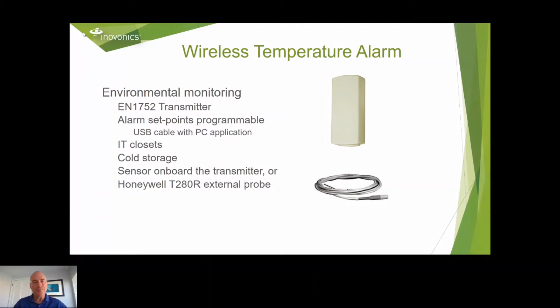Then you can also go to our website, download our program for that transmitter, which uses a USB cable, goes into your PC, and then connects onto a 3-pin header on the transmitter, so that you can change those high and low set points. You can also choose if you want to use the onboard thermistor, which is the temperature sensor, or use this pictured coil here. That's a Honeywell T280R temperature sensor, which you can put into an environment that you want to sense temperature, for example, inside a freezer or a refrigerator case in a grocery store, or, for example, in a medicine refrigerator in a hospital. So, wireless temperature alarms.